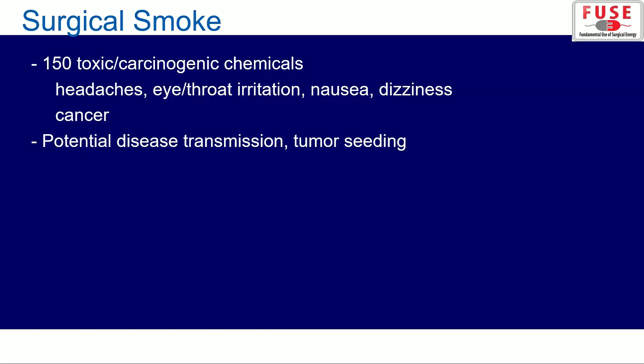Depending on the state you work in, you may have to use a smoke evacuator. At this point, 18 states have passed surgical smoke evacuation legislation, which mandates use of surgical smoke evacuation systems during all procedures likely to generate surgical smoke. Even in 2025, I think they added 4 or 5 new states to these surgical smoke evacuation mandated legislations.